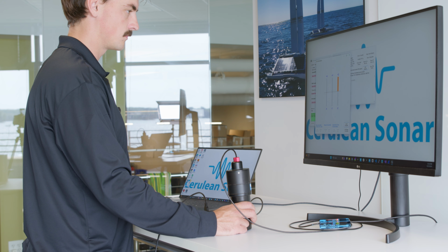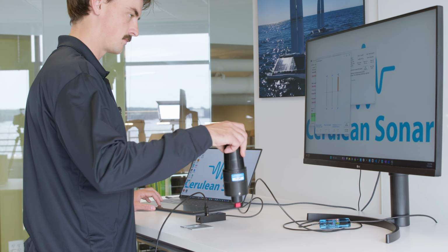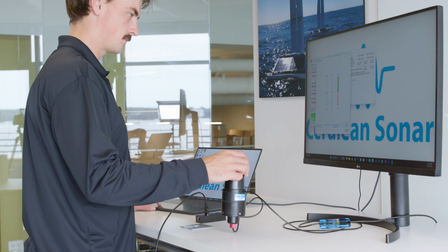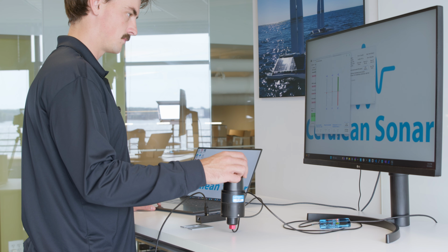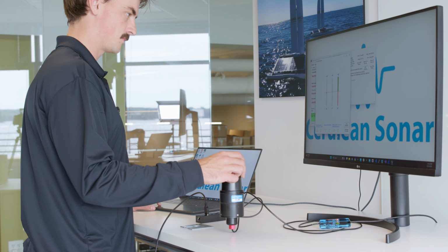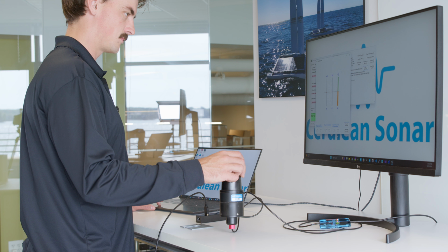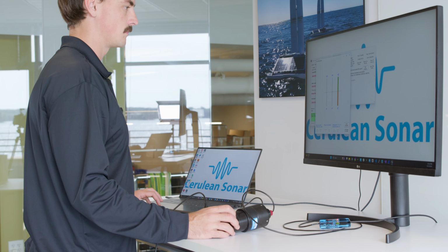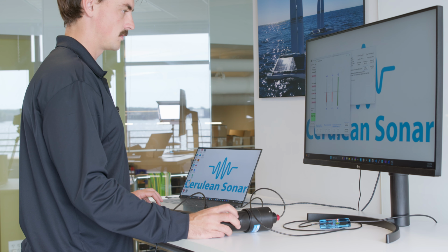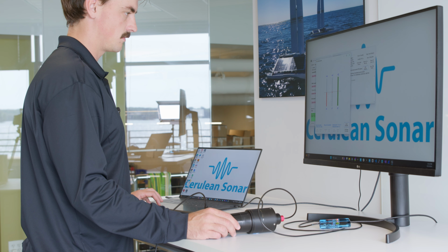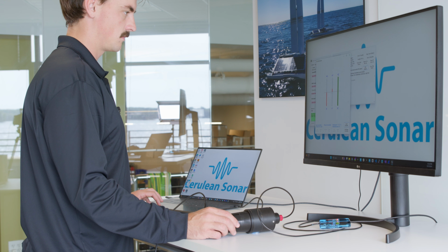The objective is to align the axes with gravity to capture the maximum signal in both the positive and negative directions. Since there are 3 axes, and we need the max signal in both directions for each, you'll need to position the device in 6 different orientations. The device will need to be kept stable in each position long enough to collect data, which is about 1 second. You can use the cap mounting screws to reference the X and Y axes, with the Z axis running vertically through the receiver.